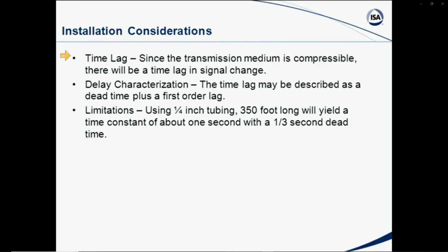For instance, in pneumatics, there will be a time lag. The transmission medium, in this case air, is compressible, and there can be a time lag in the signal change from the time that it's called for till it actually takes effect. In fact, tests run on pneumatics indicate that the time lag is going to be like a little dead time plus a first order lag, very similar to many process control loops. And this time lag, or dead time, can also be a driving function that determines the dynamic characteristics of the control loop that must be taken into account at the time that you're actually tuning the loop or using the loop.